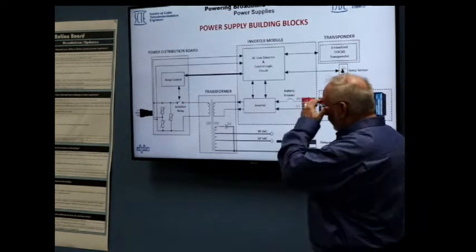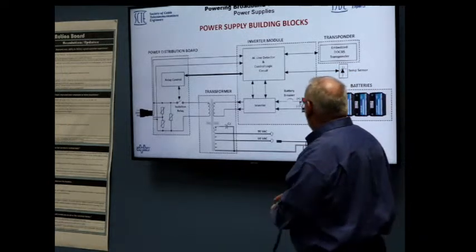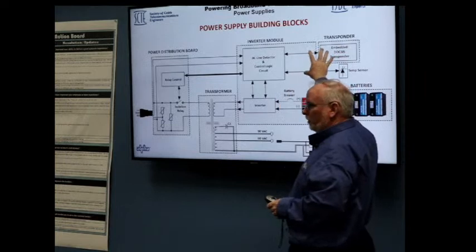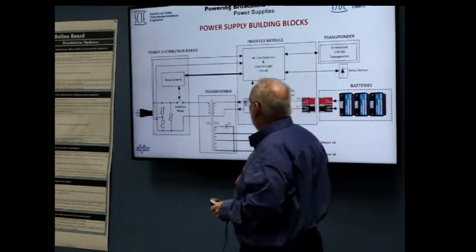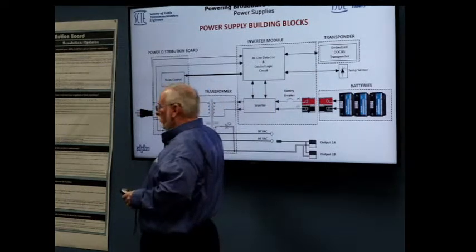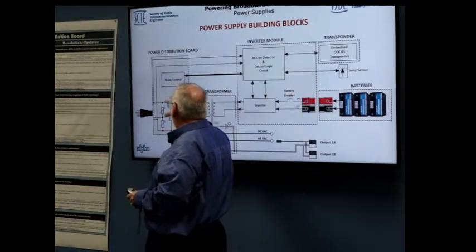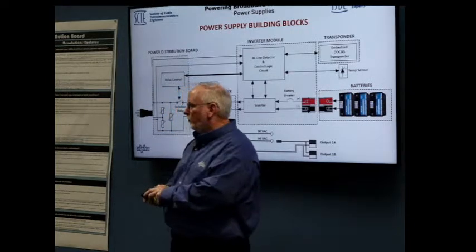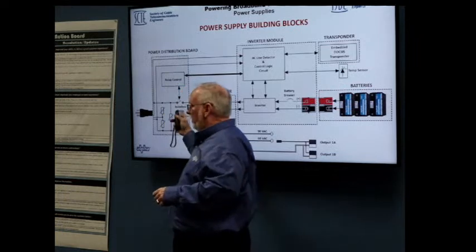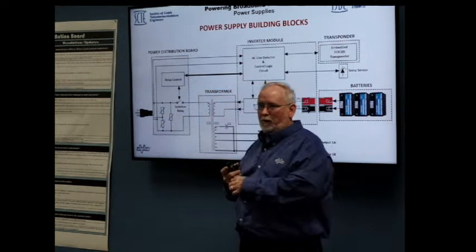So when we start to look at how things break out, again, what you're looking at over there is more or less the embedded DOCSIS transponder section. But effectively, you have your input. There's a surge protection circuit here. This is a very important thing. It's called the line isolation relay or isolation relay. This is what makes it so that we can run a UPS on the AC power line.